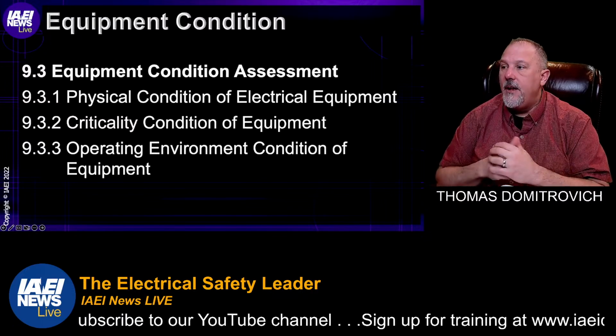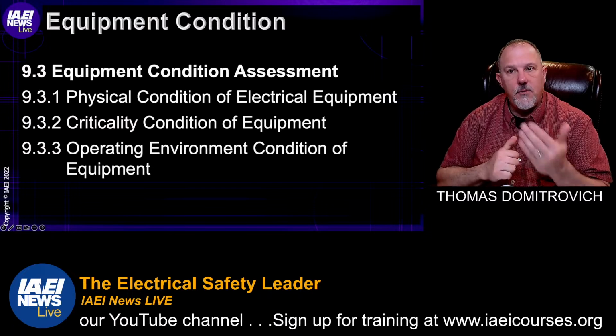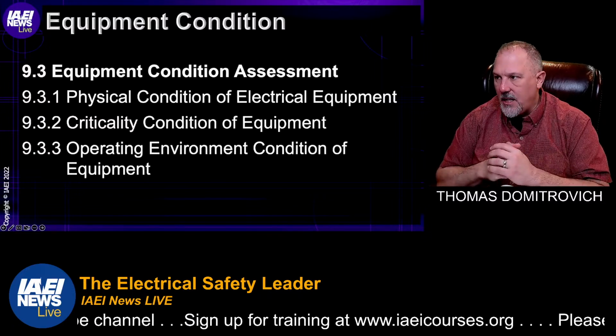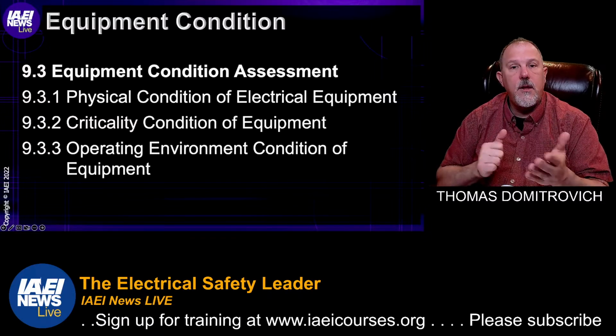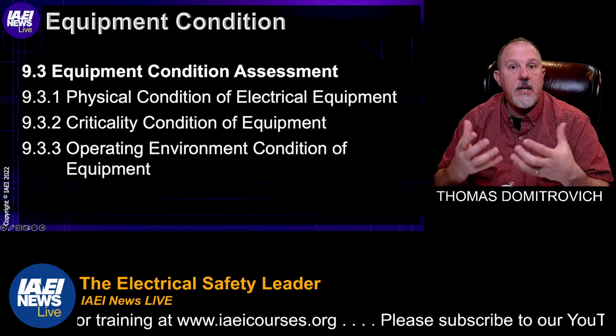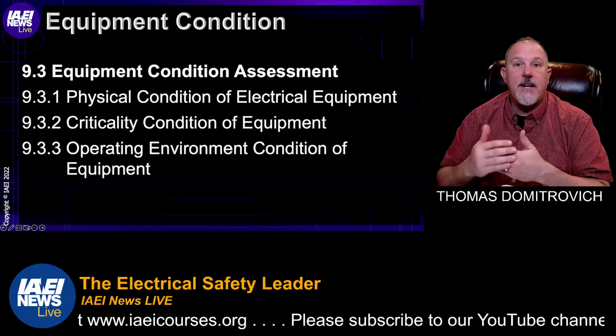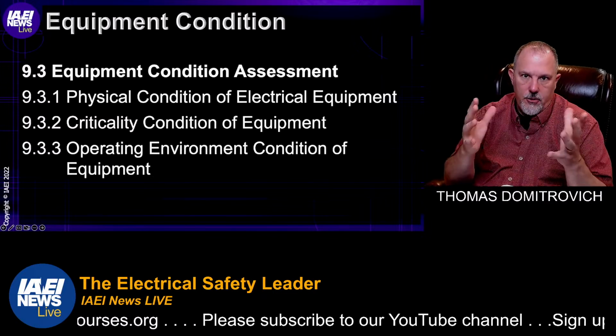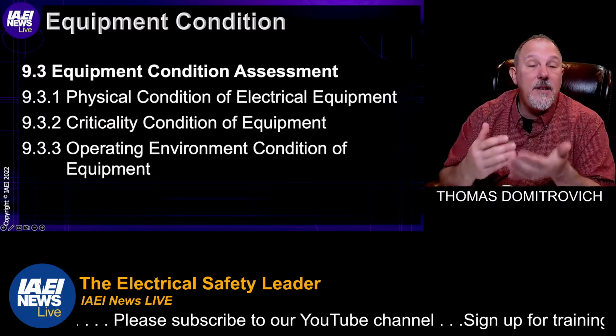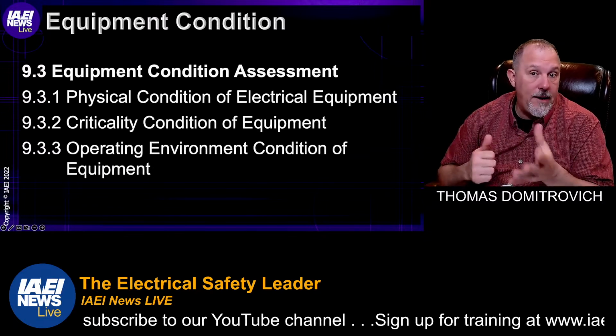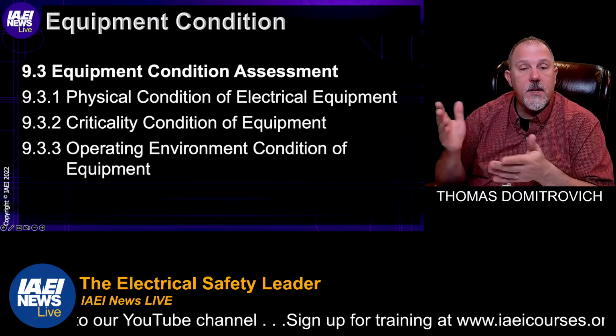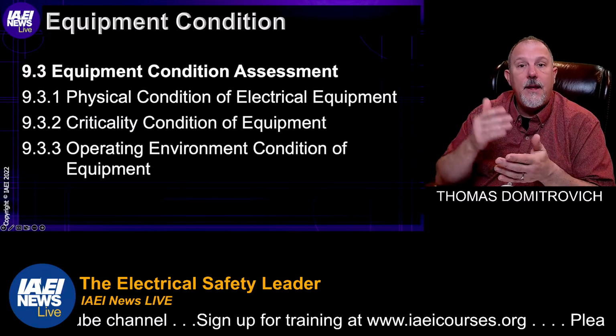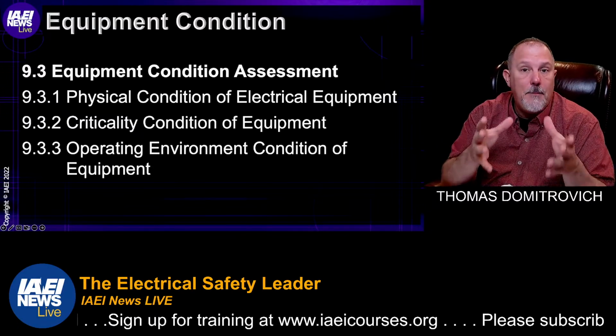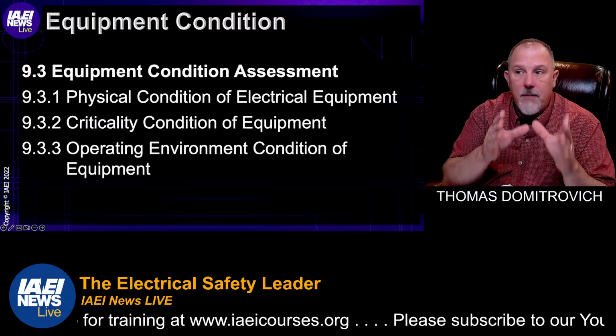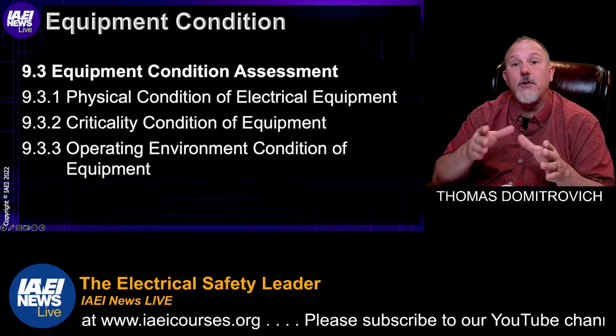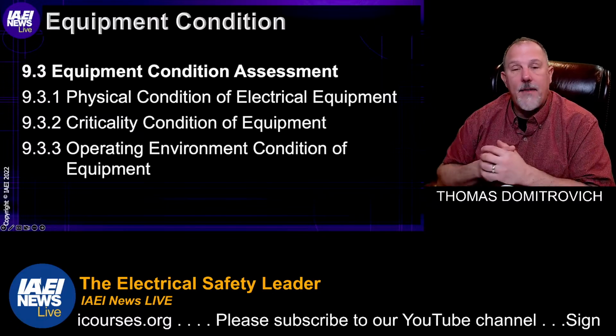There have been notifications from the continuous monitoring system. There are active recommendations for predictive techniques. So what happens if I'm measuring the humidity and temperature and I'm getting alarms that my temperature is high in this enclosure around the panel board, or maybe my humidity has gone through the roof for whatever reason? Those would be alarms that are coming in, and if I see those alarms on a panel board, that single panel board might have a physical condition 2 because of those alarms, but other panel boards in and around that area may not.